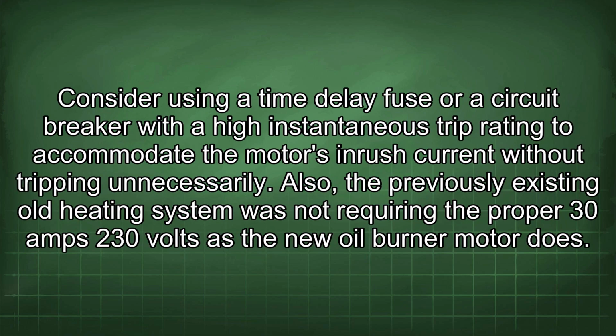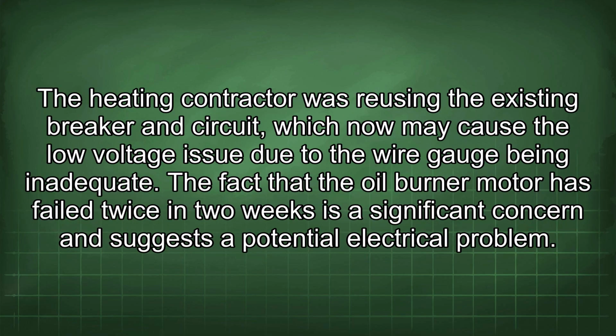Consider using a time delay fuse or circuit breaker with a high instantaneous trip rating to accommodate the motor's inrush current without tripping unnecessarily. Also, the previously existing old heating system was not requiring the proper 30 amps 230 volts as the new oil burner motor does. The heating contractor was reusing the existing breaker and circuit, which now may cause the low voltage issue due to the wire gauge being inadequate.